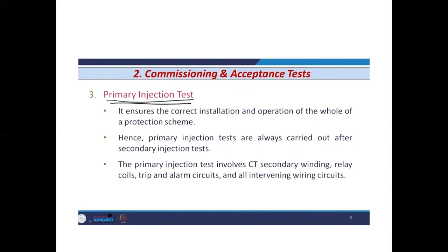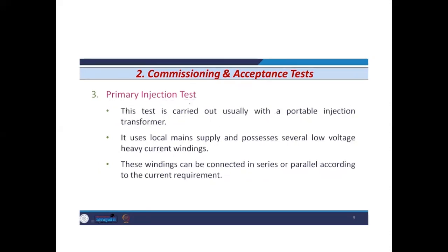The primary injection test involves the CT secondary winding, relay coils, trips, and alarm circuit, and all intervening wiring circuits. So all these tests will be performed for the relay. This test is carried out usually with a portable injection transformer. Power transformers are bulky and heavy, so a special type of transformer is to be provided for the testing purpose. Such transformers are portable, and these types of transformer are provided by the manufacturers in order to carry out the primary injection test.